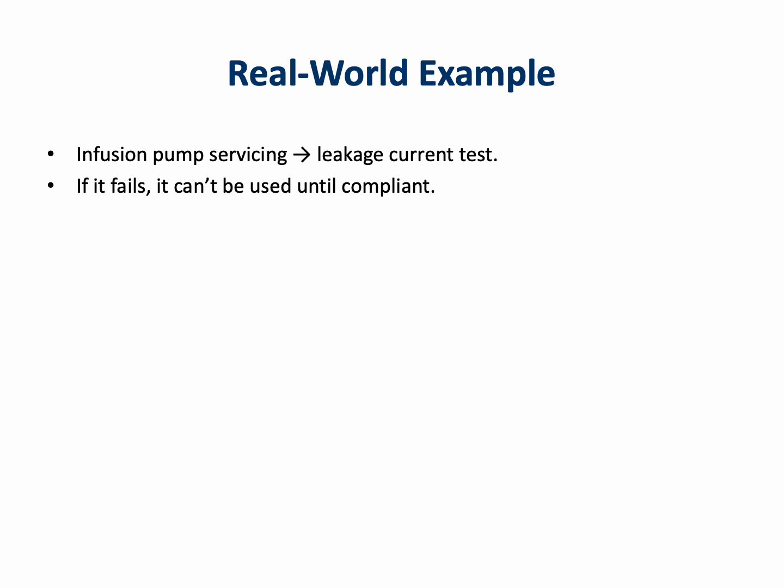For example, when I'm servicing an infusion pump, I might run a leakage current test. And if that fails, that pump can't go back to clinical use until it's compliant. So that's IEC 60601 in action. So it kind of protects patients behind the scenes.